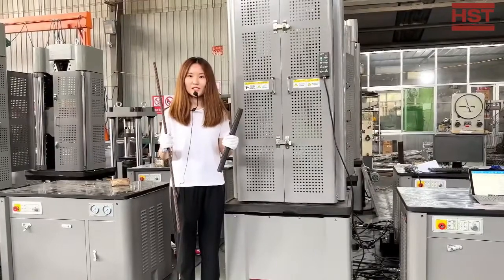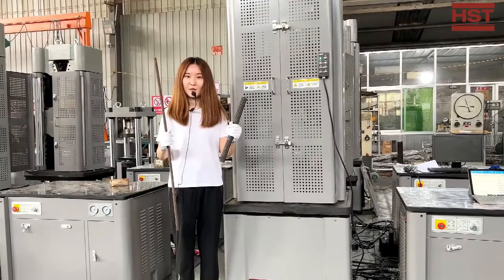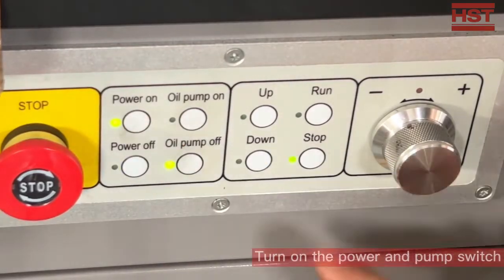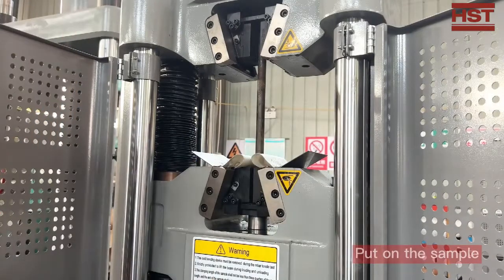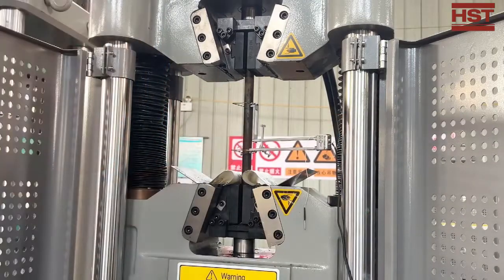Today we're going to do the test for these two materials: one is for the steel bar and one is for the steel strand. First step, turn on the power and pump switch. Second step, put on the sample. Third step, put on the electronic extensometer.